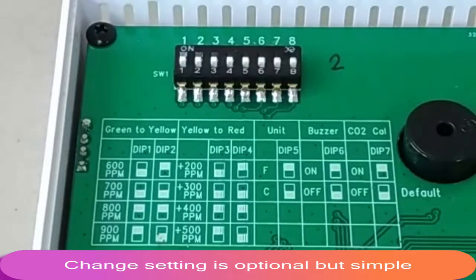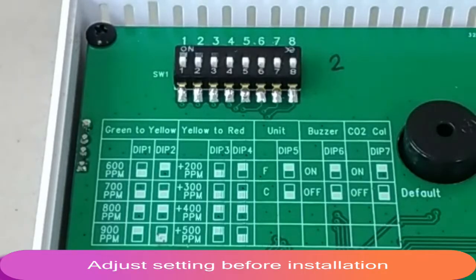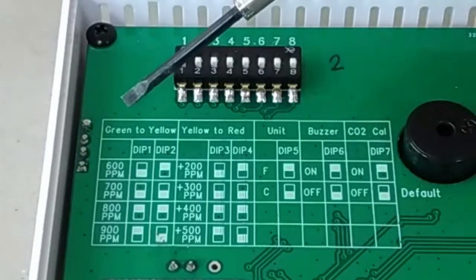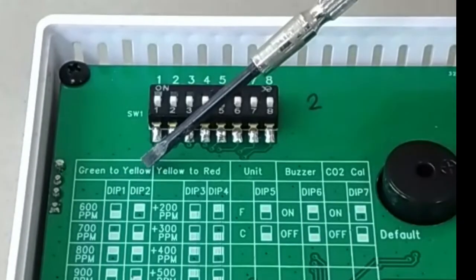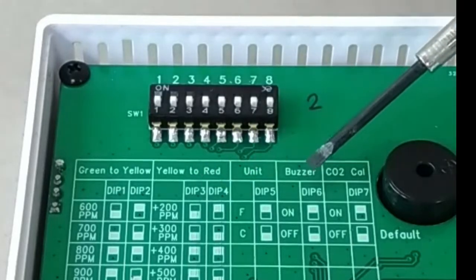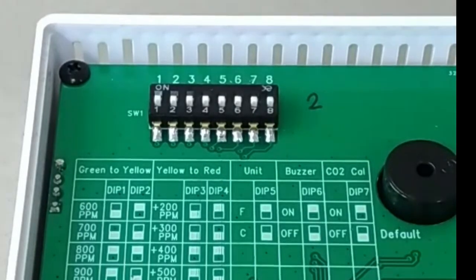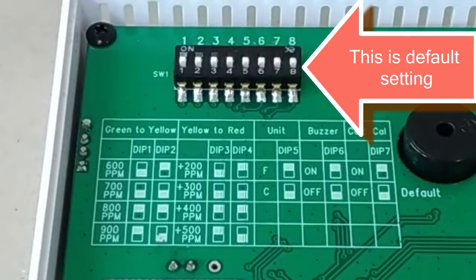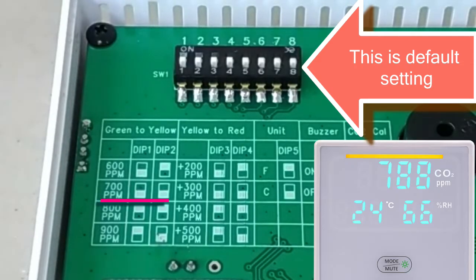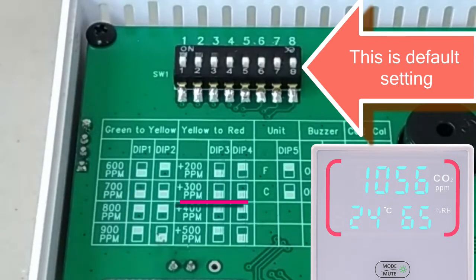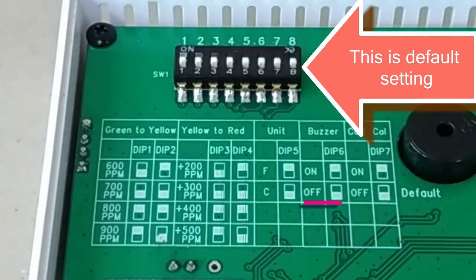The monitor allows adjustments to customize it to suit all requirements. Please do the required adjustment before installation. The adjustable parameters are yellow LED threshold, red LED threshold, temperature unit and buzzer on or off. These settings are also detailed on the PCB. The default is the light bar turns yellow while CO2 is more than 700 ppm and turns red while CO2 is over 1000 ppm, temperature unit is degree C, buzzer is off.